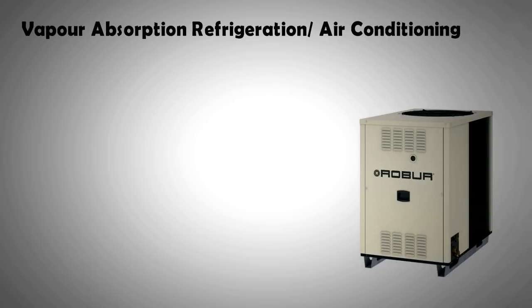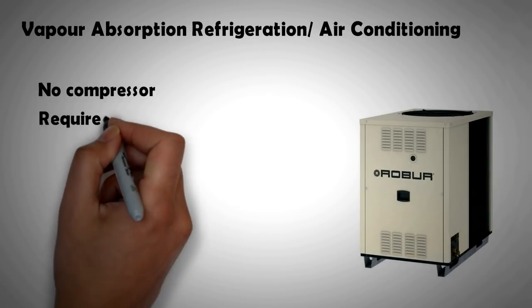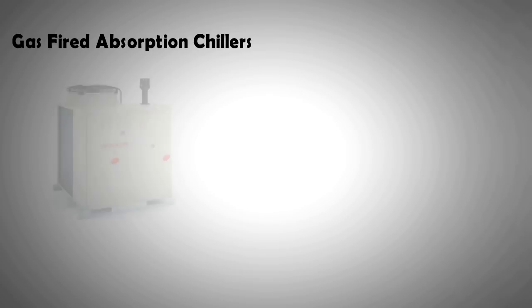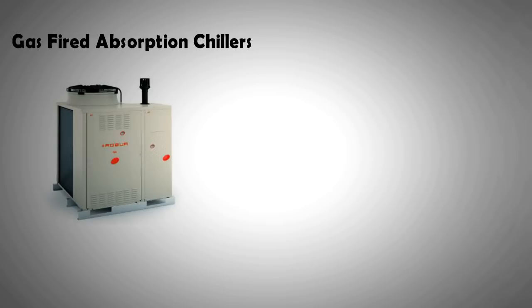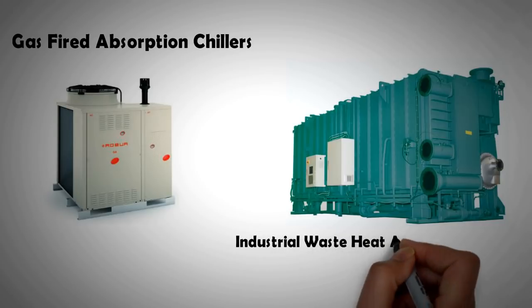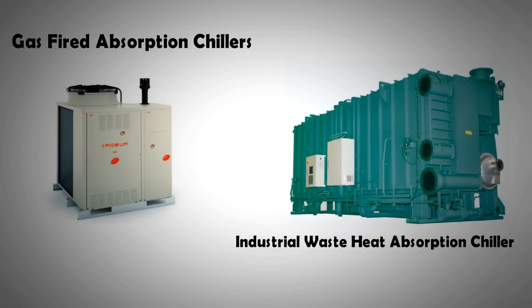Till the 1960s most of the air conditioners were based on a vapor absorption cycle and they burned gas as the source of heat. It was later that more compact vapor compression based units arrived and replaced them when electricity became cheaper. We still see vapor absorption based cooling systems being used in the industry as they can utilize waste heat. The term absorption chiller is used for these systems.